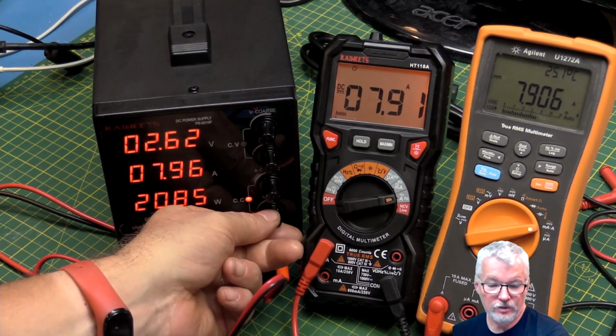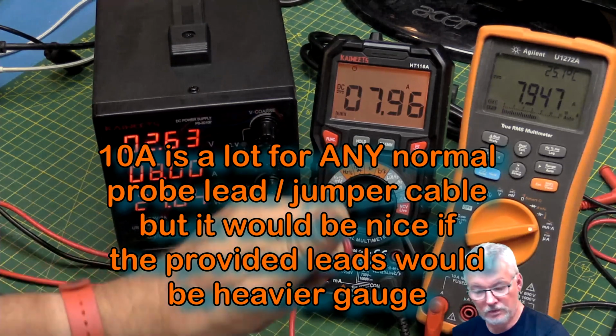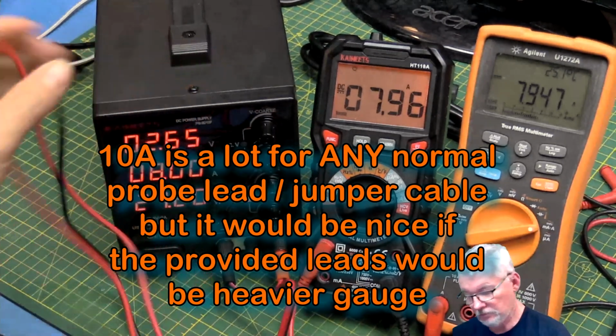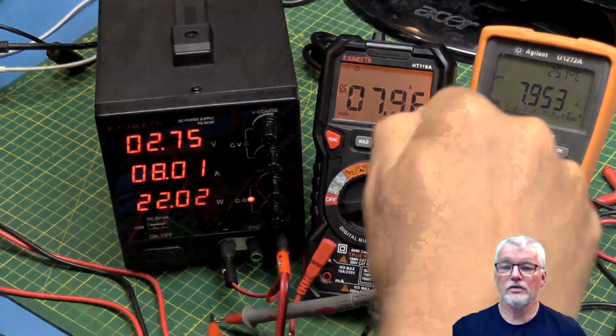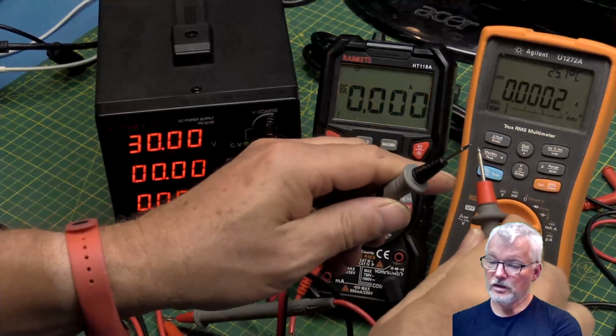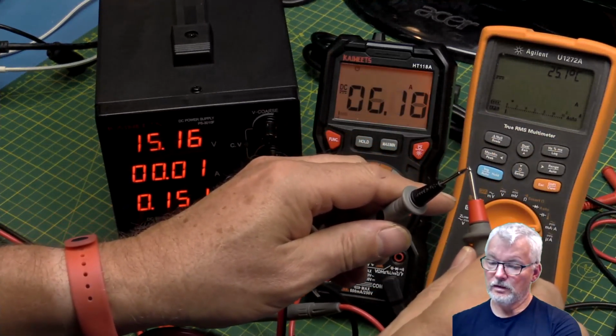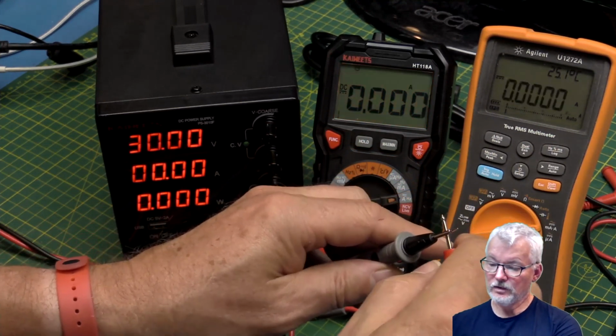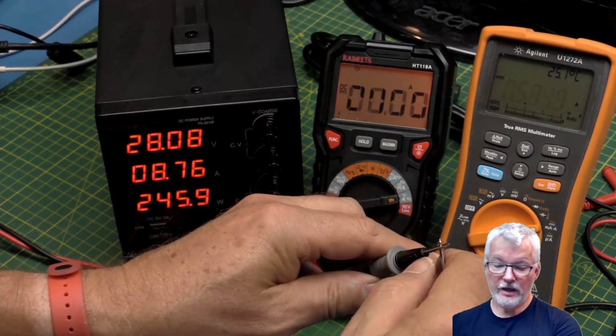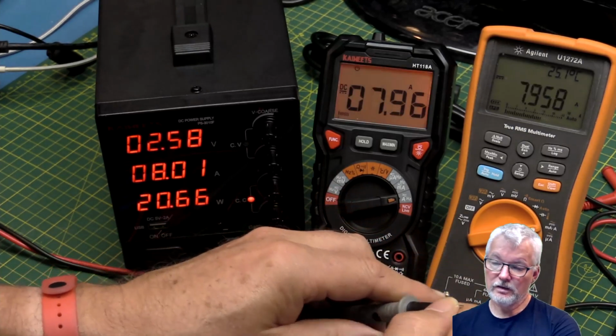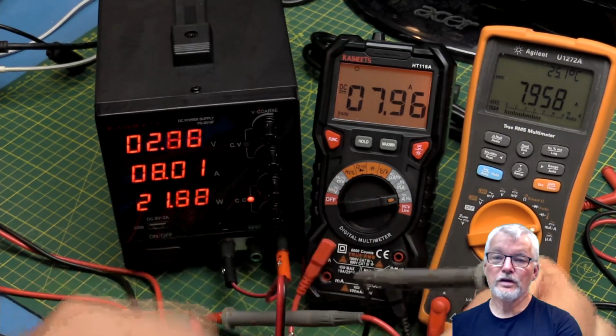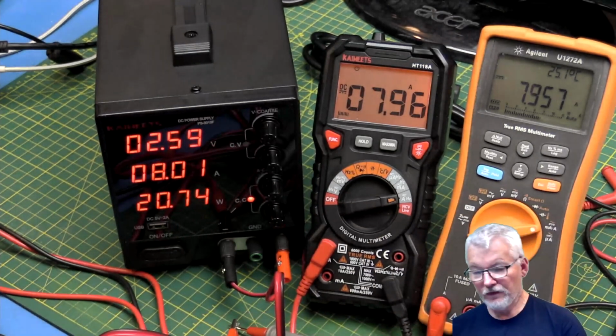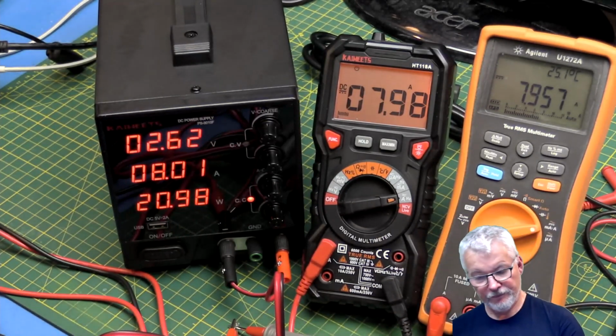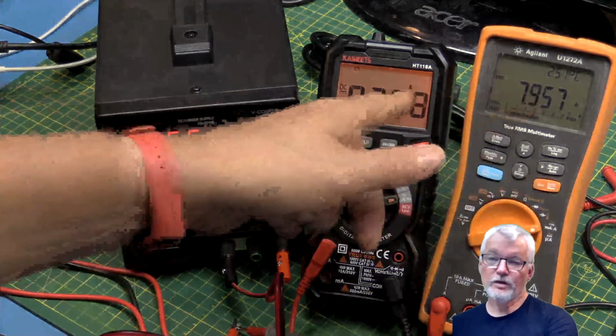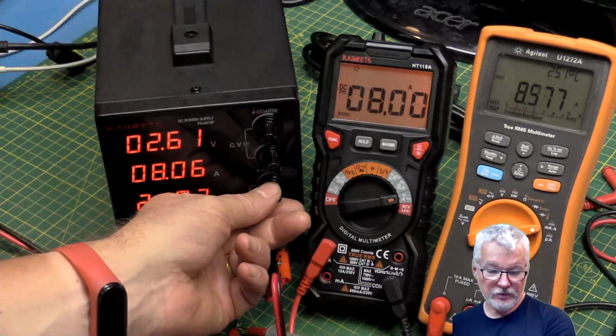I can actually feel these probes getting warm, and the cables. The connections that I'm using right here are starting to get, ooh, you can feel them welding, just because you're discharging a cap as well, so it's probably going to spike quite high. Anyway, I'm just holding the connection, so it's getting a bit warm in my fingers from the contact resistance probably. So there's 8 amps, and we're still pretty accurate here. Let's just jump now up to 10 amps.